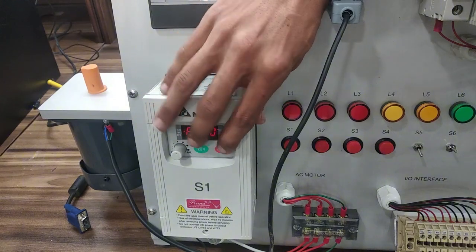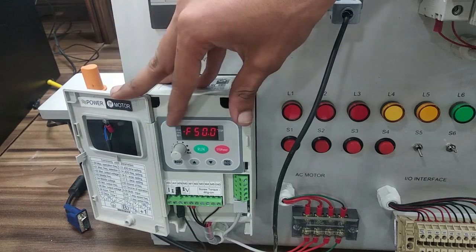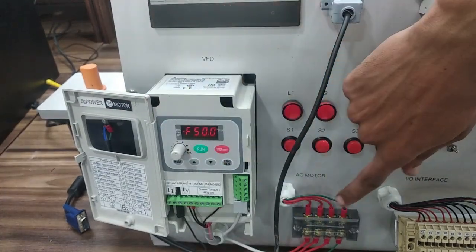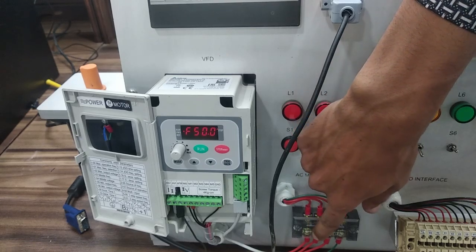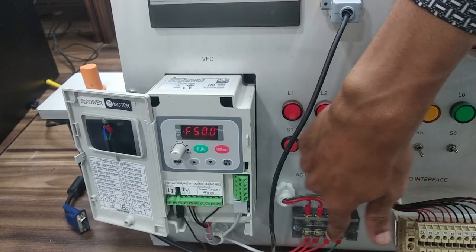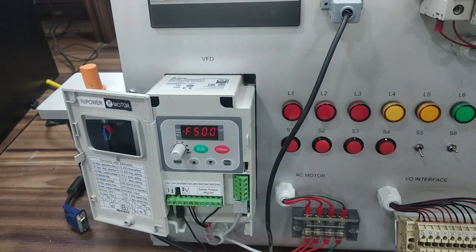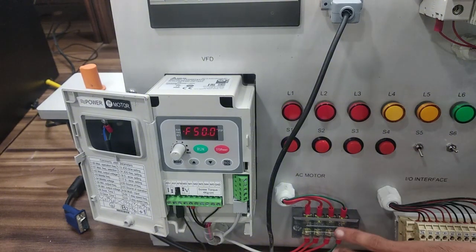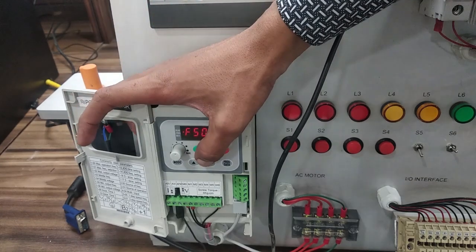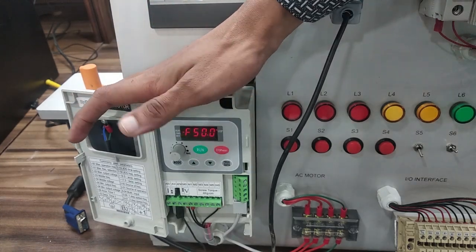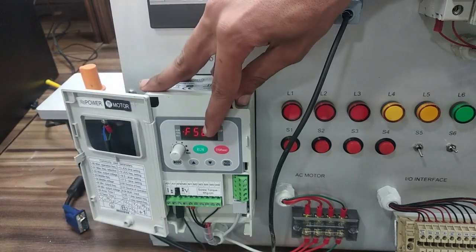Now if we just open it up like this, the induction motor is connected to this VFD using U, V, and W. As you can see the wirings here, this is a 3-phase induction motor, so U, V and W of the induction motor are connected to terminal 1, terminal 2 and terminal 3 of the VFD. So its wiring is done, and it's the common of the induction motor. We don't need to wire the circuits. Now we can control the induction motor using this digital keypad here.